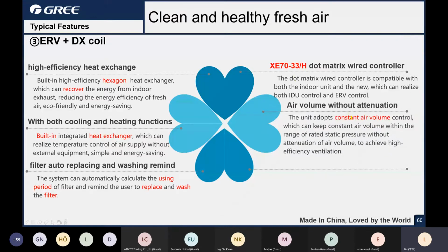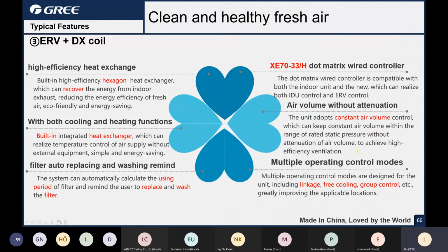And this is constant air volume. Okay, so that means the air supply is constant no matter the parameter. The fan motor will automatically adjust the speed to make sure the volume is constant. And for the control, it can be linkage control with the regular indoor unit, or free cooling by the heat exchanger, or group control by the central controller.